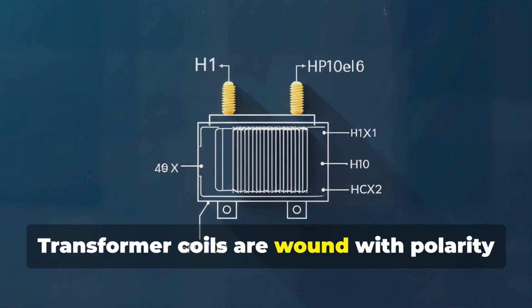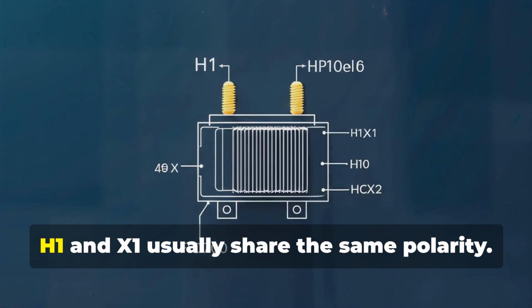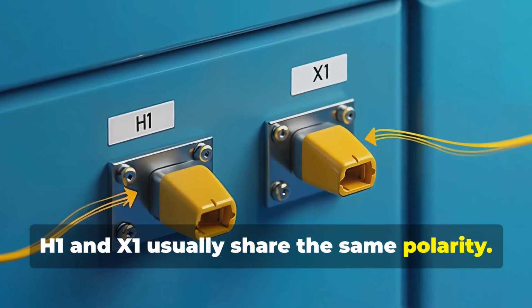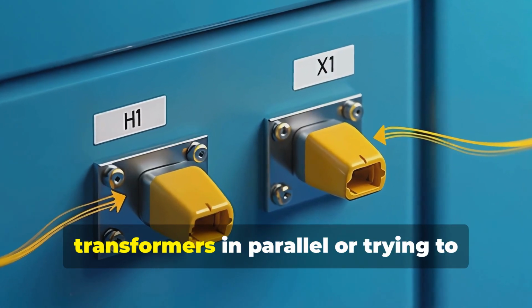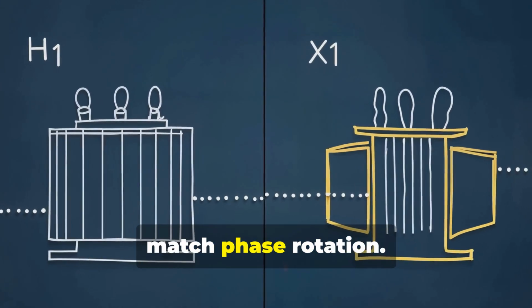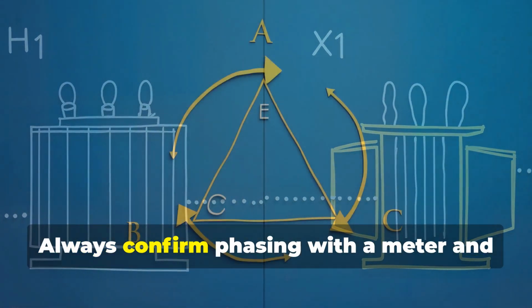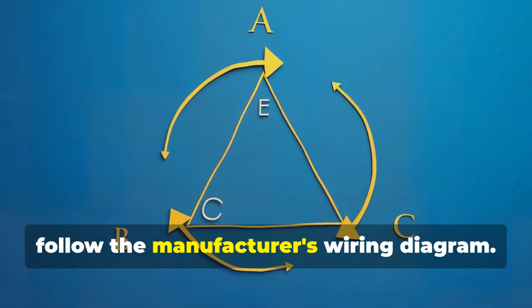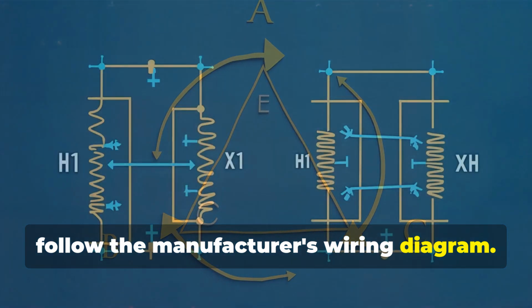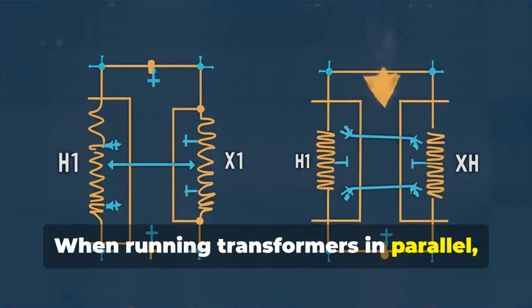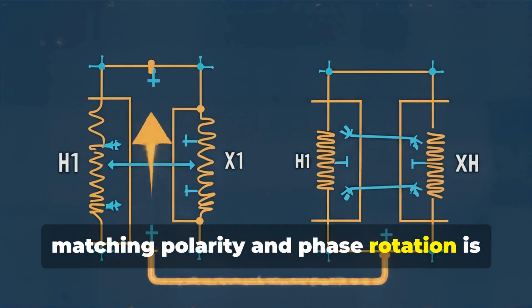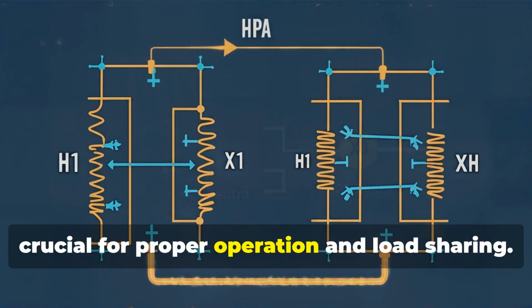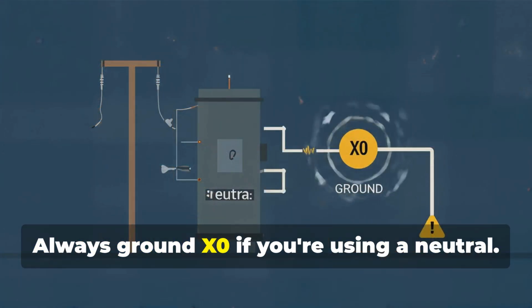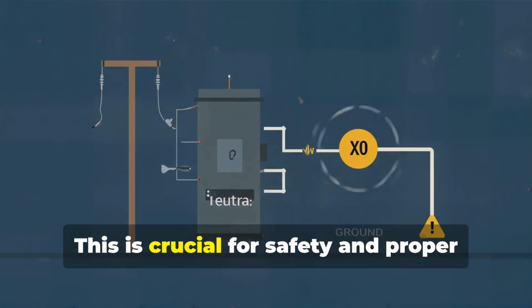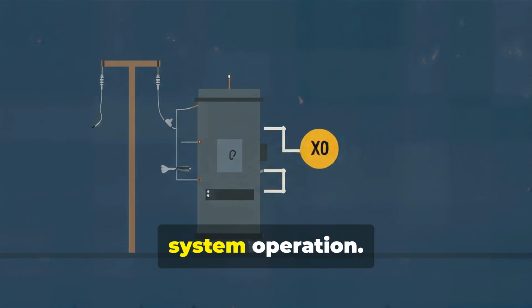Transformer coils are wound with polarity in mind. H1 and X1 usually share the same polarity. That's important if you're running transformers in parallel or trying to match phase rotation. Always confirm phasing with a meter and follow the manufacturer's wiring diagram. When running transformers in parallel, matching polarity and phase rotation is crucial for proper operation and load sharing. Always ground X0 if you're using a neutral. This is crucial for safety and proper system operation.